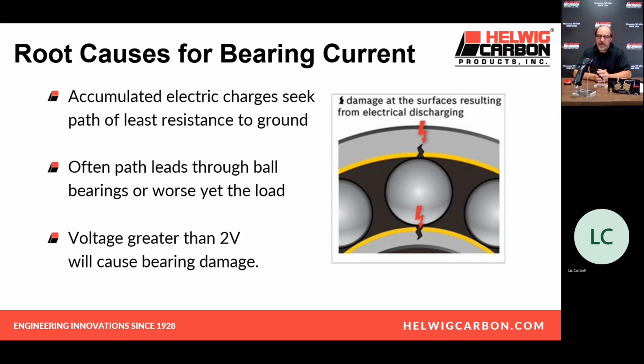Root causes, again, the accumulated electric charges build on the bearing and it finds a path of least resistance to ground, that is typically through the drive end bearing, though it could be through your gearbox or any connected equipment.